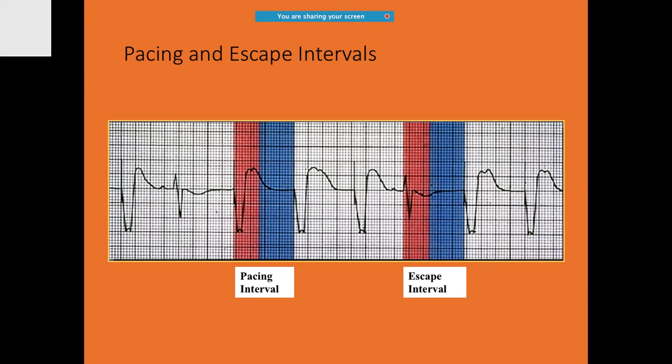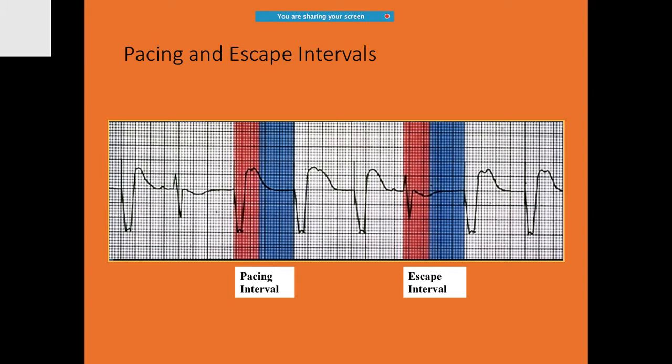The pacing interval is the time between two pacing spikes. The escape interval is the duration between an intrinsic beat and the next paced beat — after an inherent beat occurs, the pacemaker waits (sensing for any incoming beat) and if none comes, it paces. These are the two key concepts: pacing interval and escape interval.